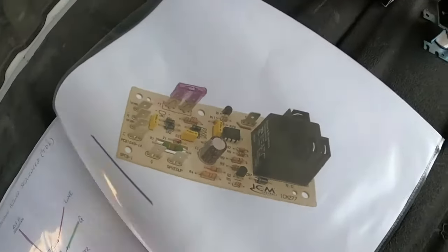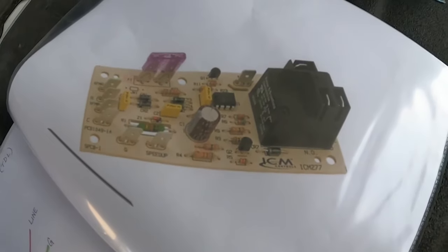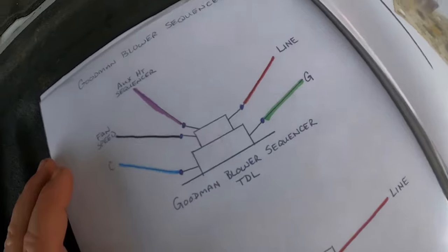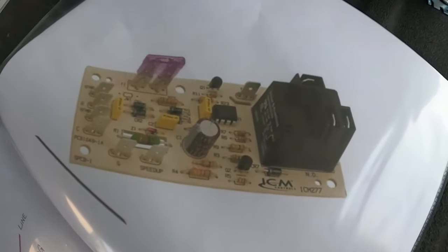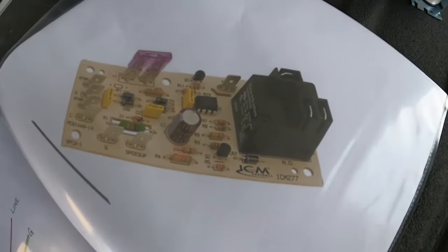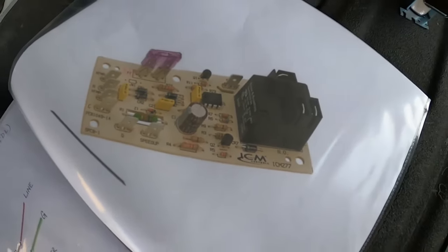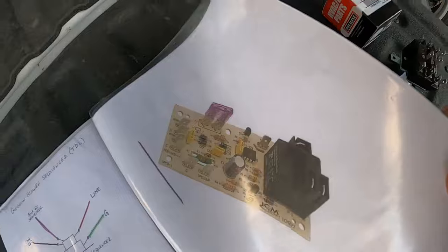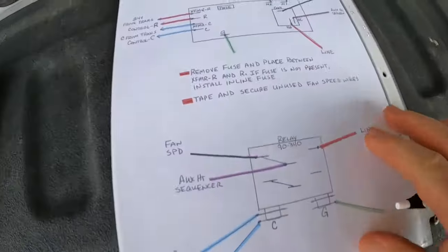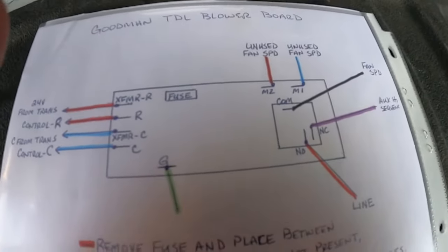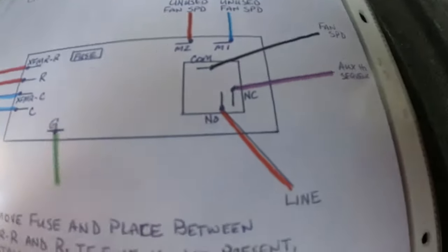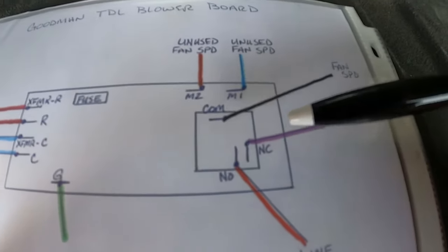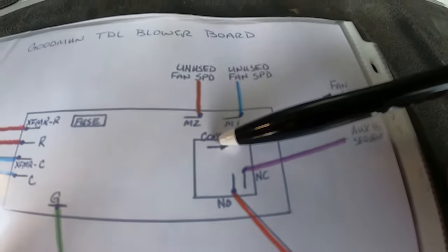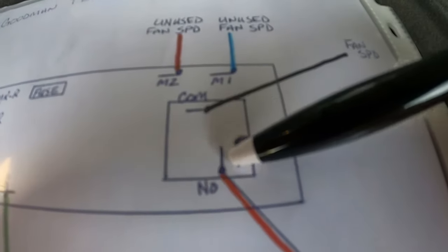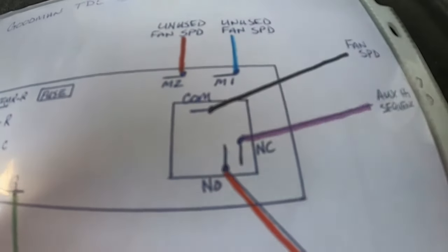The next one is going to be the Goodman. The board they replaced this with, I mean, you find them burnt, you find them melted, but there is a fuse, so that's going to be a difference in this situation. So here is how that board is laid out. You've got your relay. In this situation, you're going to have a common, and you're going to have a normally open and a normally closed.